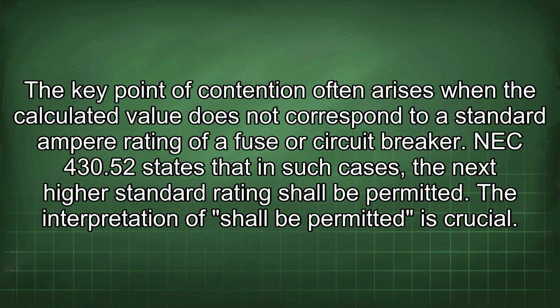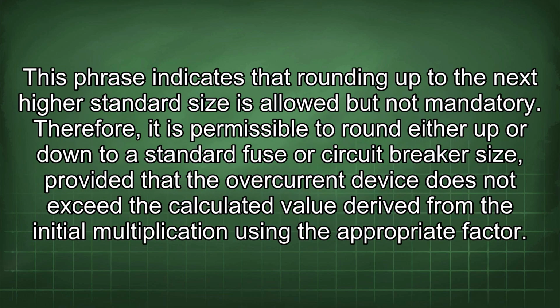The key point of contention often arises when a calculated value does not correspond to a standard ampere rating of a fuse or circuit breaker. NEC 430.52 states that in such cases, the next highest standard rating shall be permitted. The interpretation of "shall be permitted" is crucial. This phrase indicates that rounding up to the next higher standard size is allowed but not mandatory. Therefore, it is permissible to round either up or down to a standard fuse or circuit breaker size, provided that the overcurrent device does not exceed the calculated value derived from the initial multiplication using the appropriate factor.